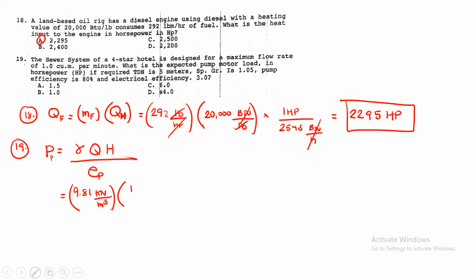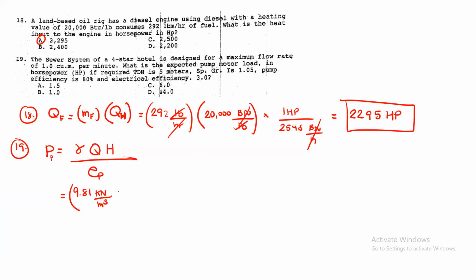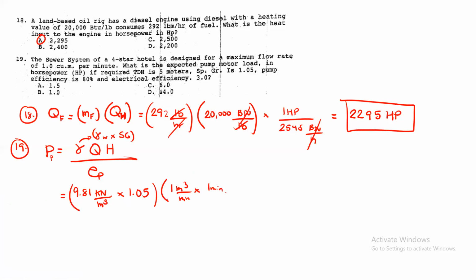So ito is yung specific weight pala natin, i-times pa natin ng specific gravity. So specific weight ng water times specific gravity na 1.05 times 1 cubic meter per minute. So times 1 minute per 60 seconds, i-convert lang natin to seconds. Then times height. So ilan yung height natin? So 5 meters. So yan yung TDH. So divided by pump efficiency na 80%. So makakansel dito yung meter cube. So kilonewton meter is kilojoule per second is kilowatt.